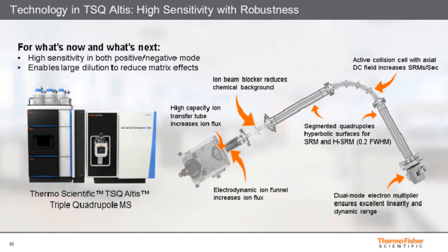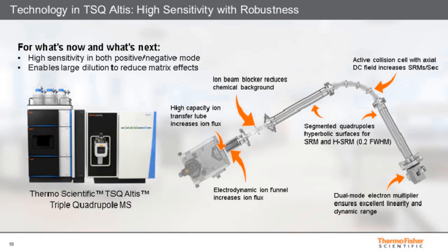The triple quadrupole used in these experiments was the TSQ Altis. There is a lot of new technology in this instrument — innovations in the ion source, mass analyzer, and RF electronics offer high sensitivity, reduced noise, and more data points with high SRM rates, allowing confident quantification of compounds at extremely low concentrations in the most challenging matrices such as food. The system offers very high sensitivity in negative mode, which is crucial for reaching low concentration levels for anionic pesticides. Novel ion optics reduce chemical background via ion beam blocking and source design, increasing robustness, reducing maintenance, and improving reproducibility.